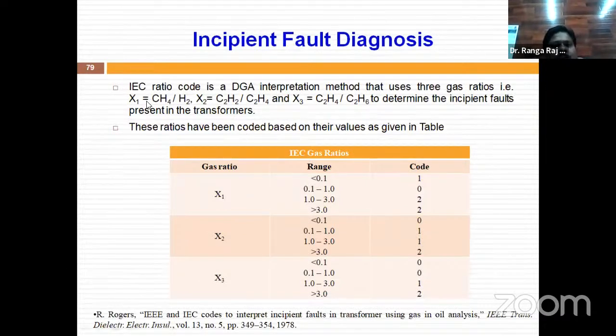So first, there are three inputs in this method: x1, x2, and x3. x1 is CH4 by H2, these values come from the DGA test. We pick the sample, collect it from the transformer, perform the DGA test, and get these values. That is clear, right? X2 is C2H2 by C2H4. X3 is C2H4 by C2H6, right? So determine these three values, x1, x2, x3.